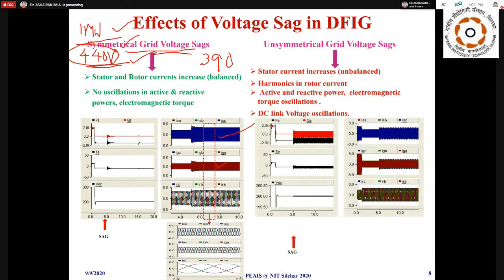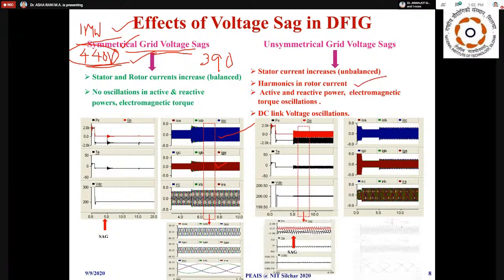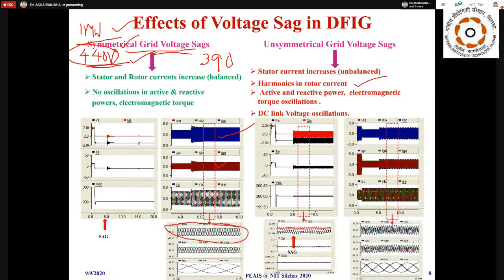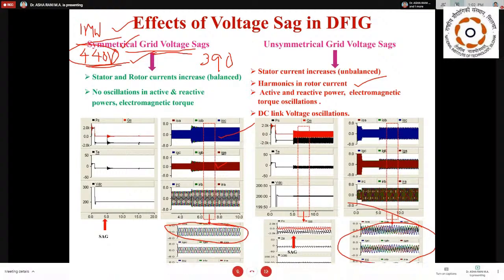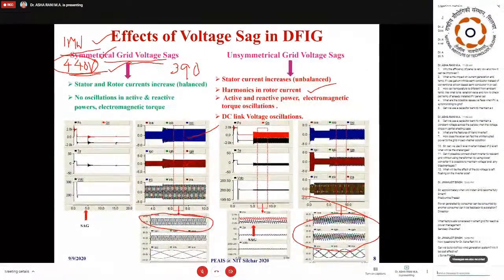You can observe here, during unsymmetrical sag, a lot of disturbance will be there in the machine in terms of oscillations of 100 hertz. I will explain this in detail in the upcoming slides. In addition, there will be harmonics in the rotor current, and you can see that your stator currents are unbalanced with a lot of issues. Whereas this was very smooth, here the scenario is different. Active and reactive power, electromagnetic torque oscillation, DC link voltage, so a lot of issues will come.